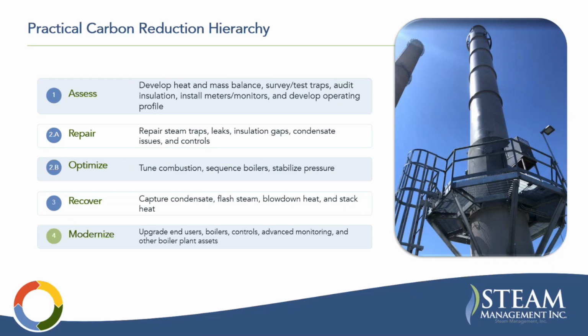So you could capture additional condensate by reconfiguring return systems, capturing flash steam, blowdown heat recovery, additional stack heat recovery. All of those require some projects, right? So that's why that's number 3. And then modernize, and then you're talking about actually replacing equipment, upgrading end users, boilers, controls, implementing advanced monitoring systems, and replacing other boiler plant assets.